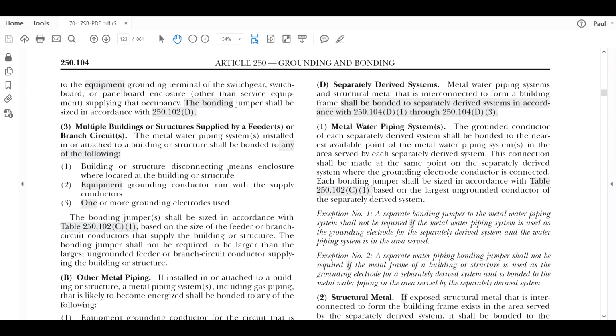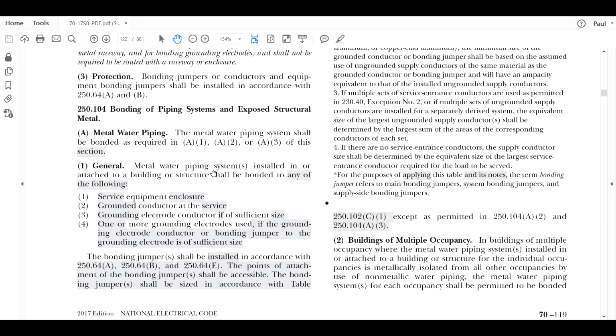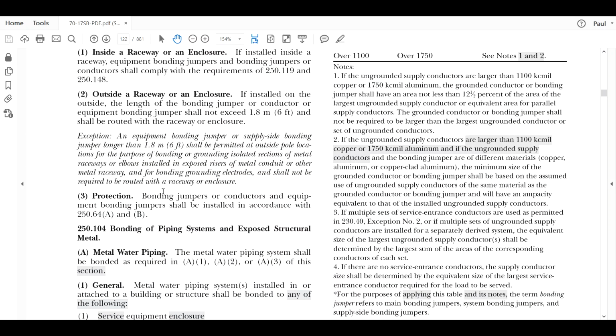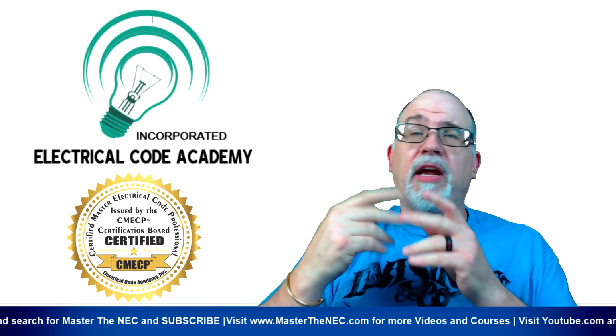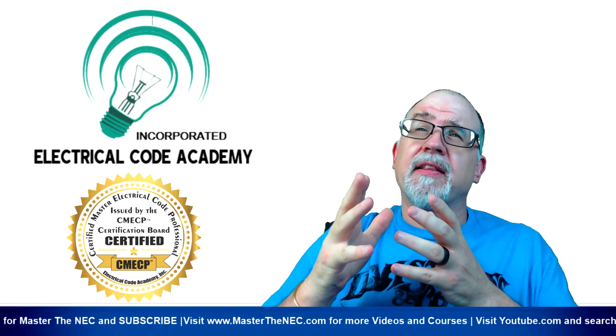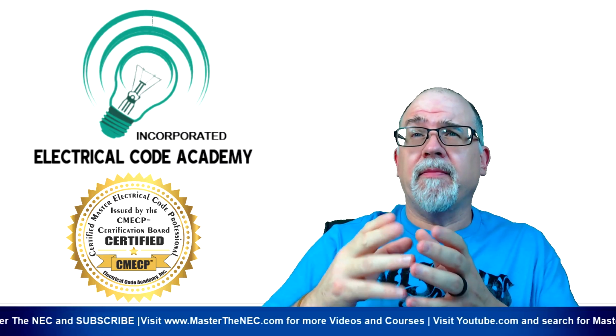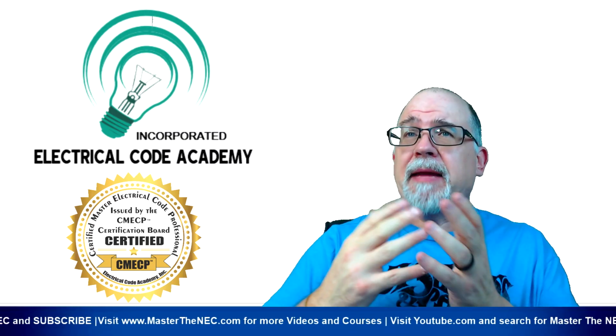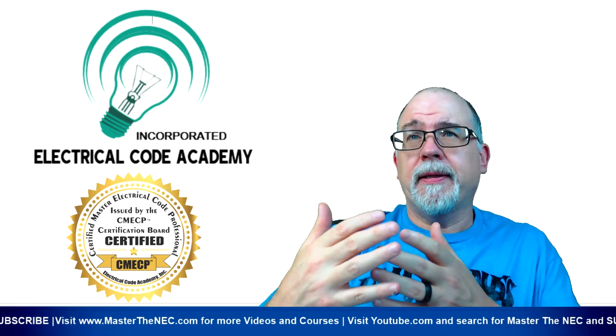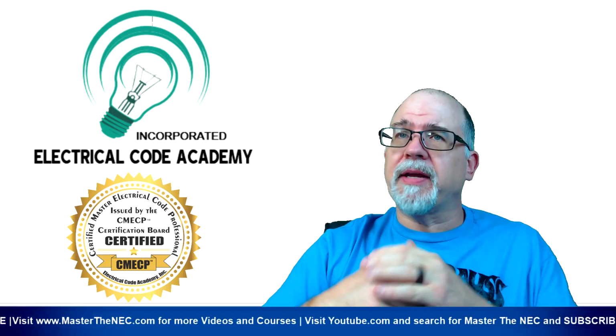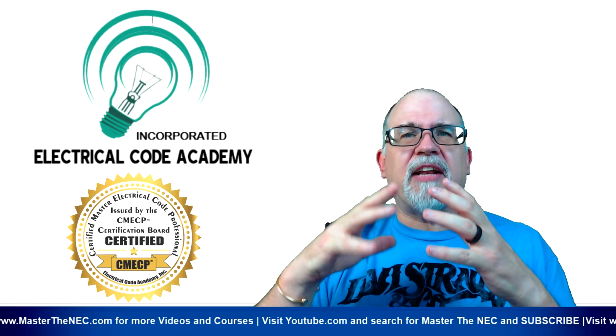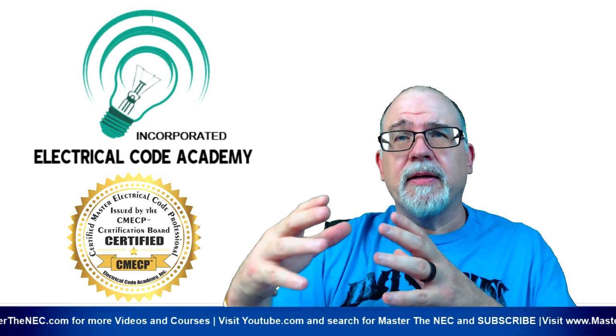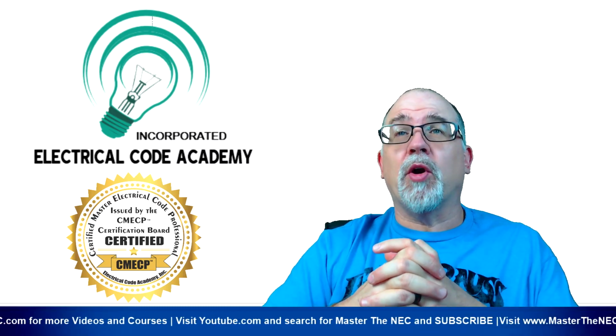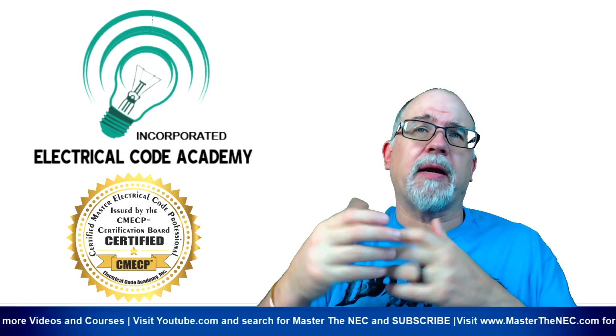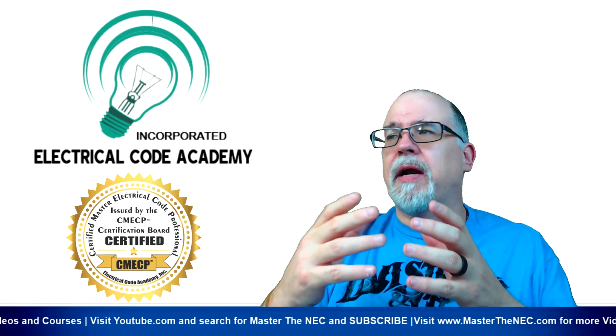So, I'll talk to you about one more thing. What if we have a transformer that's in a building that has metal water piping, or metal framing of the building, and it's exposed? Okay, so we've got the metal water piping in the building, and it's in an area where that transformer is serving that area. Then we're going to look at 250.104, and we're going to learn a little bit about what to do. So this is a building where I might have the transformer.